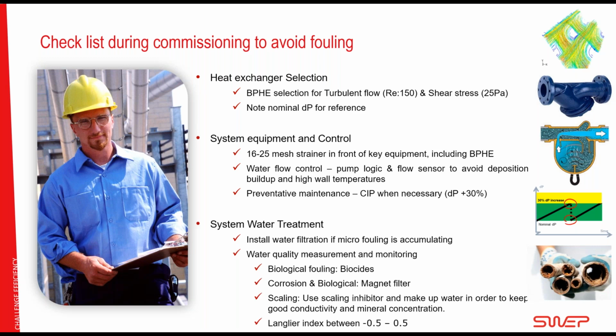I have gone through this before, so I will not do it so much, but now you know what I mean with Reynolds 150. This is the starting point. If you can reach 500, please do. Shear stress 25. If you're at a shear stress of 10 pascals, don't panic. If you're at 2 pascals, don't panic. If you have a clean and controlled closed loop system, this is for when you don't know, right? When you're building a system but you don't really know where it's supposed to go, have 25 as a good reference point. Know your pressure drop, because maybe that's not your problem, but you should have it in your manuals. Your customers, when they install it, should measure the flow or the pressure drop so that they know what it is, and then they can compare it after 1 year, 2 years, 3 years to see, has it decreased a lot? Do I need to clean this out?